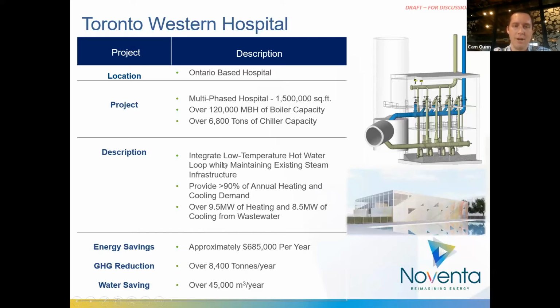So what are we doing? We're going to be ultimately providing about 90% of their annual heating and cooling demand using our wastewater energy transfer system, which equates to 9.5 megawatts of heating and 8.5 megawatts of cooling. On top of that, we're converting the hospital's entire HVAC heating system from a steam system to a low temperature hot water system, while still maintaining steam system redundancy.